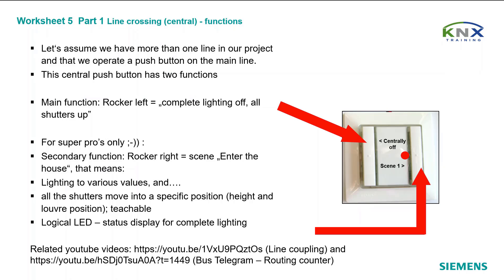Worksheet 5, Part 1: Line Crossing Central Functions. Let's assume we have more than one line in our project and that we operate a push button on the main line. This central push button has two functions: main function Rocker left equals complete lighting off and all shutters up. Secondary function Rocker right equals scene 'Enter the house', meaning lighting to various values and all shutters move into a specific position.